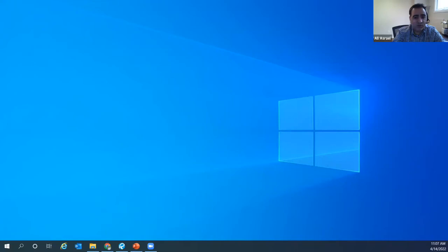If the designer is not available, we get into a whole story of another engineer coming in and doing this and that. But the discussion is, if you have a measure, are we okay with national? Do we go with 7312 only, or is 7313 still applicable? Because they're two separate sentences, both of them are applicable. So you have a measure, you follow national, but you have to follow 7313 as well, because as part of a measure, you have a smoke control system to meet the building code requirement. This was the latest discussion that we had with Chris. I believe we got a confirmation.